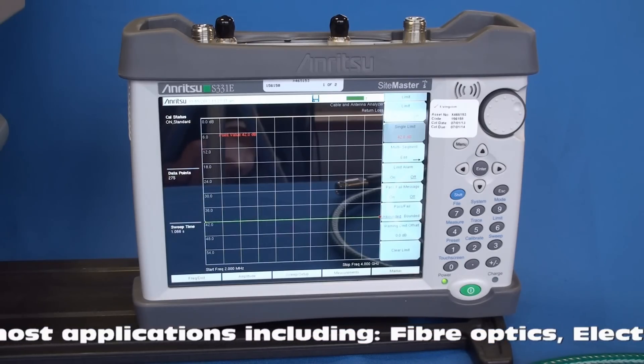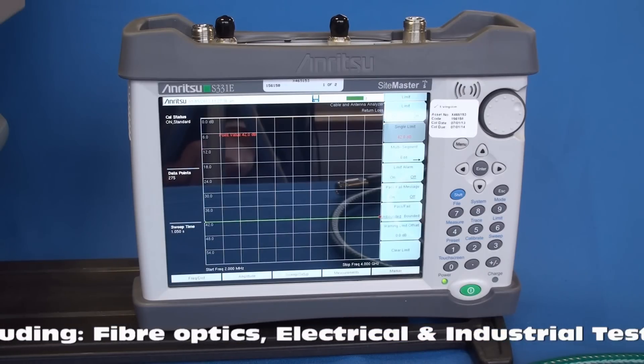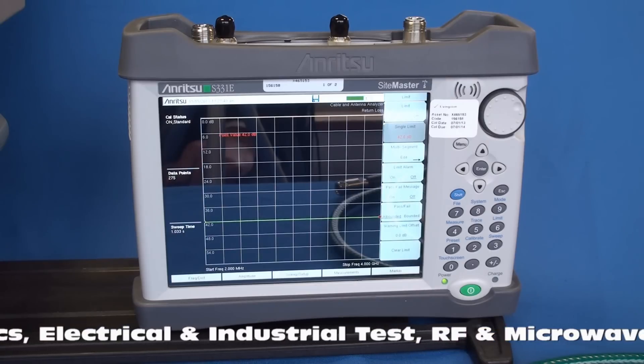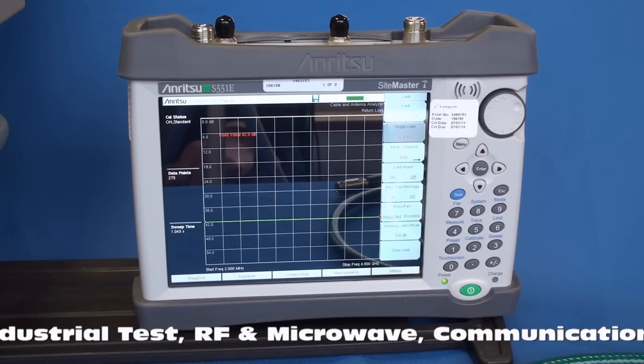Utilising measurements such as return loss, VSWR, cable loss and distance to fault, technicians are able to perform verification on and check the cabling to tower mounted amplifiers, duplexers, diplexers and filters, in addition to tuning antennas.